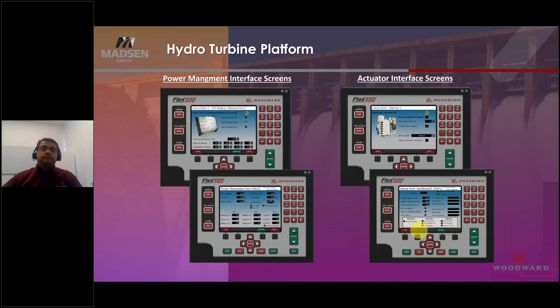This is a unique feature, because if you know you have a lot of trips under 25% of load, it might mean there's sticking within the actuation system or the gate. Sometimes a problem happens a lot, but you don't know at what condition of the machine it occurs. By getting these two features, the 25% and 75%, you can define that.